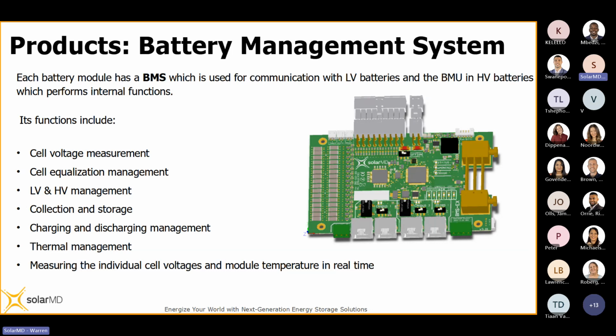However, with lithium iron phosphate, you can't take the same approach. If you overcharged a cell, it would be permanently damaged, and you can't leave a cell in a low state and have an unbalanced pack. You can think of the 16 cells inside the battery like a chain with 16 links, and the chain is only as strong as its weakest link. So one of the core functions of the BMS is to balance the voltage, or state of charge, of each of the 16 cells within that battery.